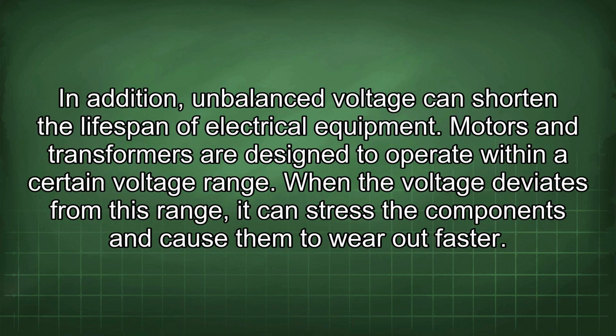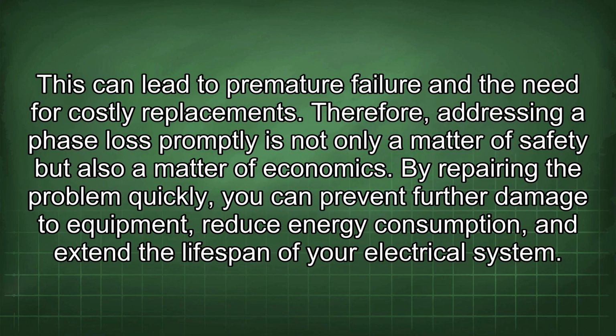In addition, unbalanced voltage can shorten the lifespan of electrical equipment. Motors and transformers are designed to operate within a certain voltage range. When the voltage deviates from this range, it can stress the components and cause them to wear out faster. This can lead to premature failure and the need for costly replacements. Therefore, addressing a phase loss promptly is not only a matter of safety but also a matter of economics. By repairing the problem quickly, you can prevent further damage to equipment, reduce energy consumption, and extend the lifespan of your electrical system.